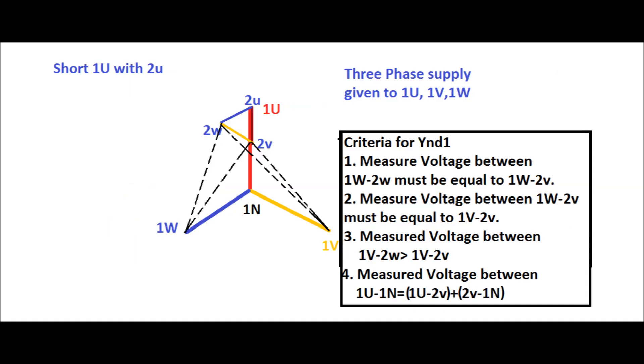The criteria to be fulfilled for vector group YND1 are as follows: Number 1 — voltage between 1W and 2W must be equal to voltage between 1W and 2V. Number 2 — voltage between 1W and 2V must equal voltage between 1V and 2V. Number 3 — voltage between 1V and 2W must be greater than voltage between 1V and 2V. Number 4 — voltage between 1U and 1N must equal the sum of voltage between 1U and 2V plus voltage between 2V and 1N.